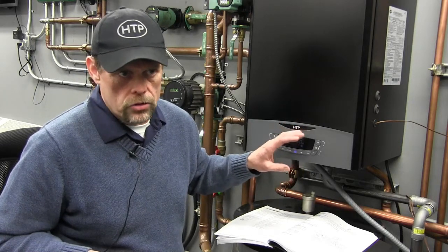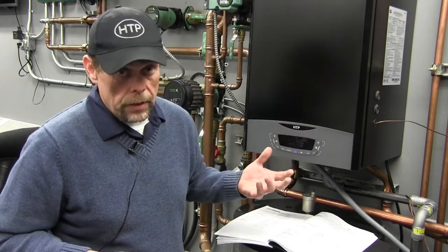So we can look at the error history, look for trends. We can, in essence, have a conversation with the boiler, and it will continue to scroll the last 10 fault codes for you. The error codes do not receive a date and time stamp on the boiler through the boiler control, so they won't be displayed through the control. However, we do have the Wi-Fi option. If your boiler is online, then all of your error codes will be date and time stamped, and that information can be accessed through the wireless app on your smartphone.